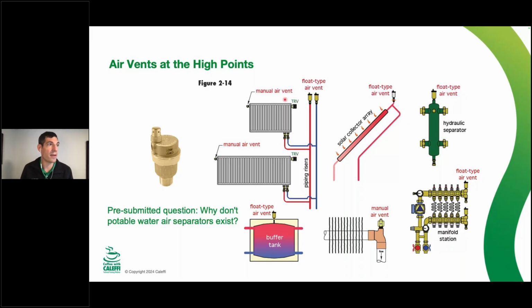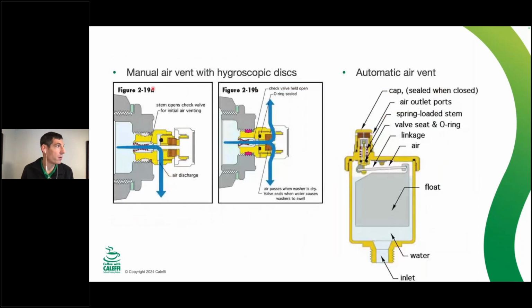So what's going on inside of an air vent? Got a very simple manual air vent that you can open up and let air come out of it if this is in the side of a radiator or something like that. And then you can twist this to an automatic mode where it's going to let air out unless water starts to come out. And then these little fiber gaskets are going to swell up and they're going to seal. So if water starts to come out, it's going to seal. Very, very simple technology for a manual air vent.